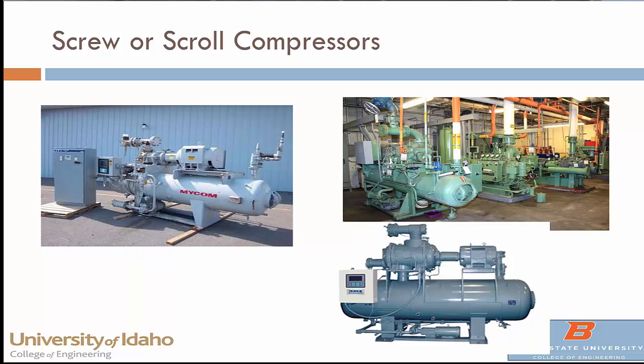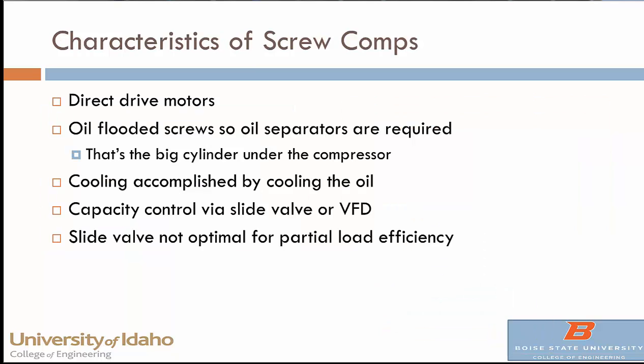Also common in compressor rooms are screw compressors. They have a direct-drive motor to a cylindrical compressor sitting on top of a larger cylindrical tank, which is the oil separator — because these are oil-flooded machines where oil is mixed with the refrigerant. Capacity control is done either with a slide valve that changes how much of the screw's length is used for compression, or with a variable frequency drive. Slide valves work reasonably well for partial load, but a variable frequency drive is better.